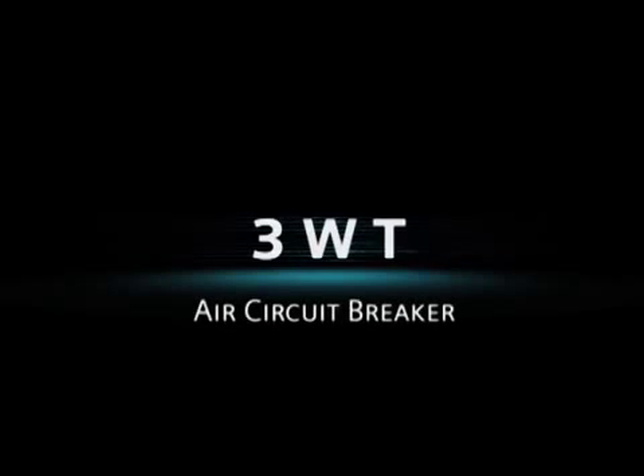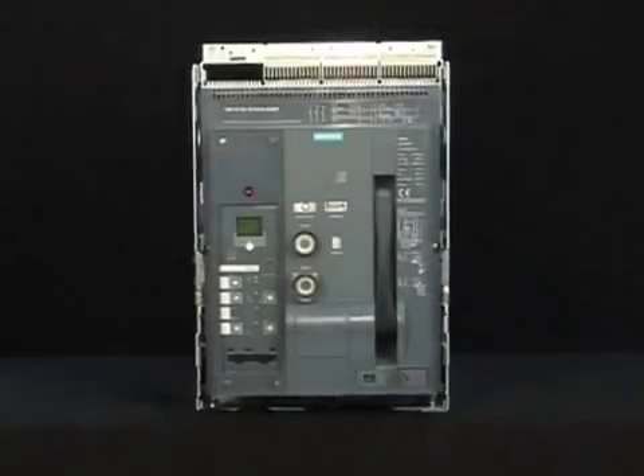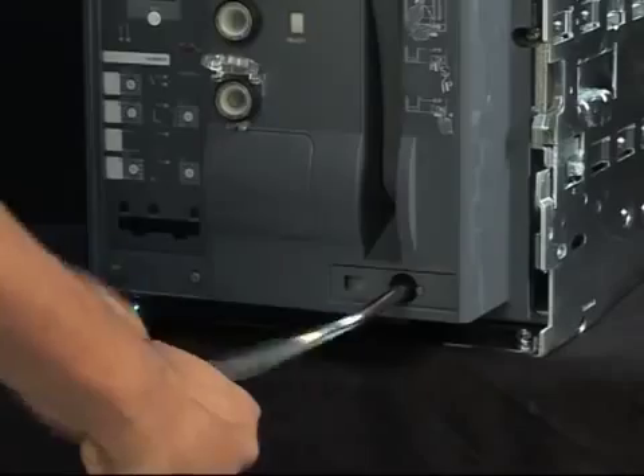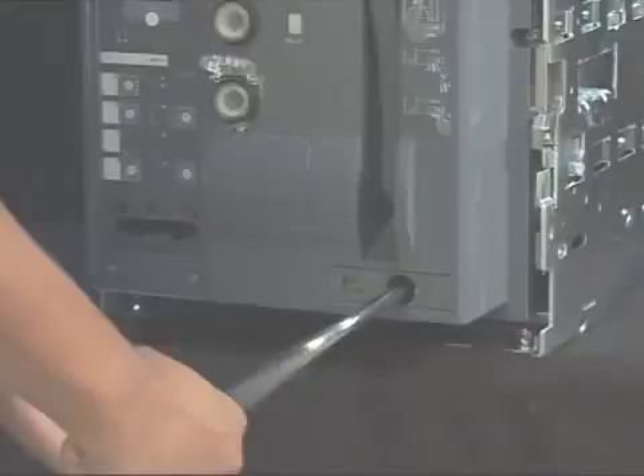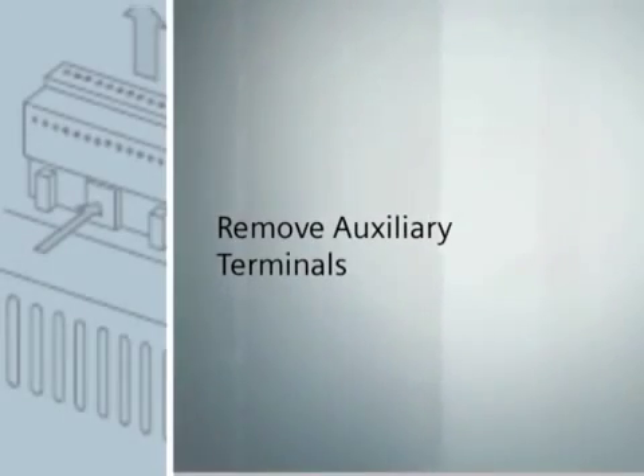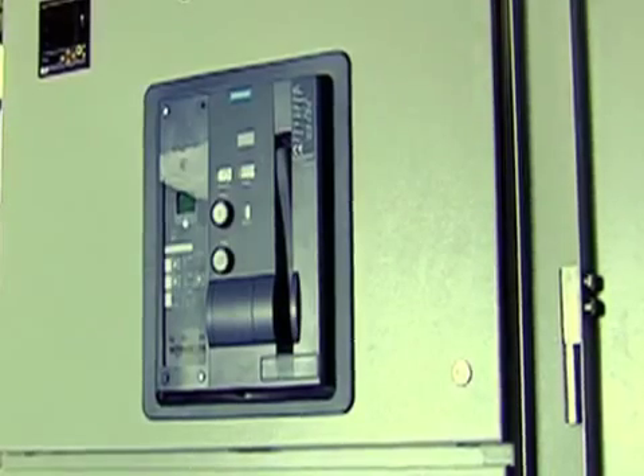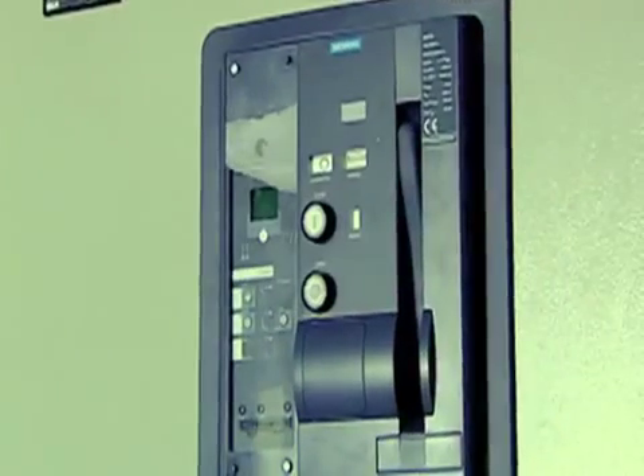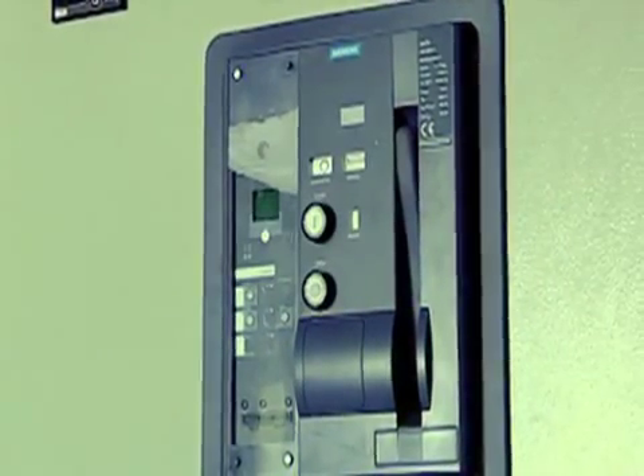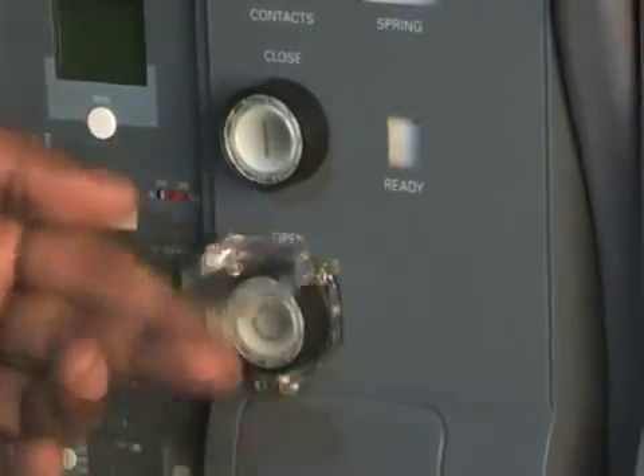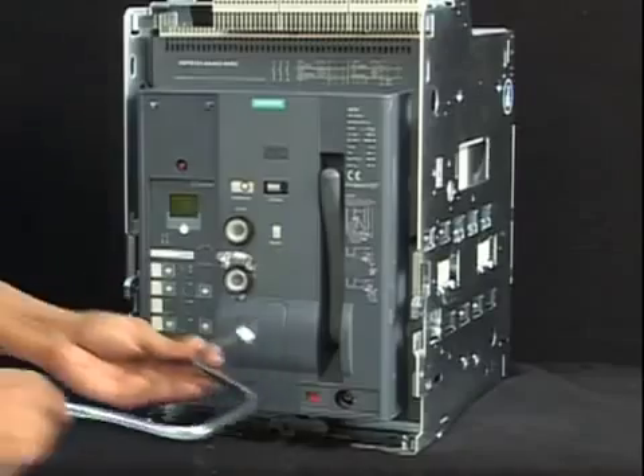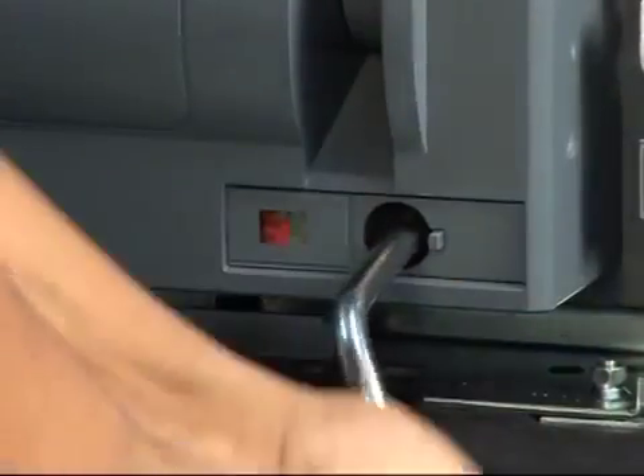Siemens 3WT air circuit breaker. As a preparation for fixing accessories for a withdrawable breaker, we need to rack out the breaker, and for a fixed breaker, we need to remove the auxiliary terminal connectors. This can be done even when the breaker is installed in the switchboard. For a withdrawable ACB, the unique safety feature comes into play. If you do not switch off the breaker, the racking shutter does not open. After this, the ACB is drawn out to the disconnected position.